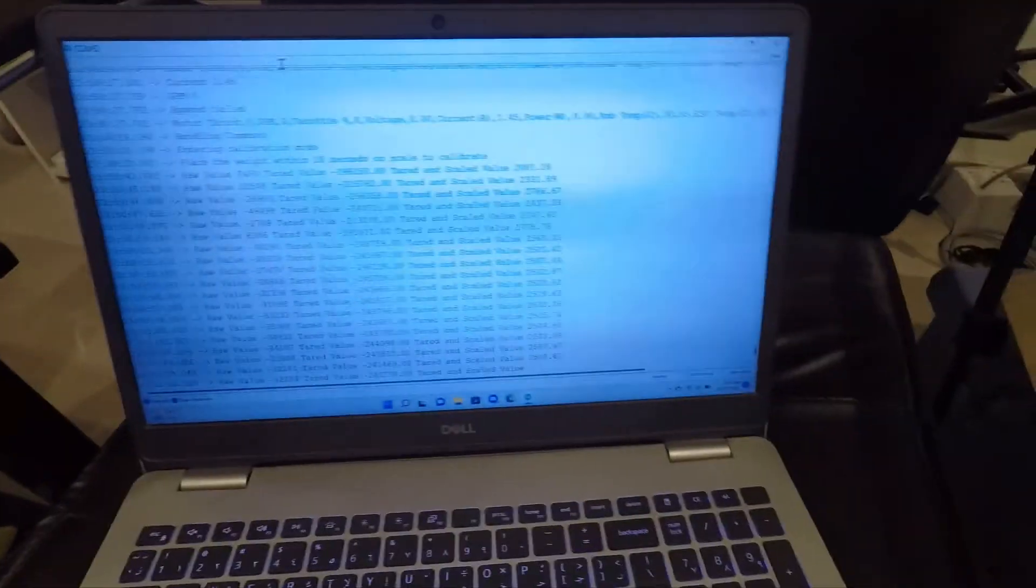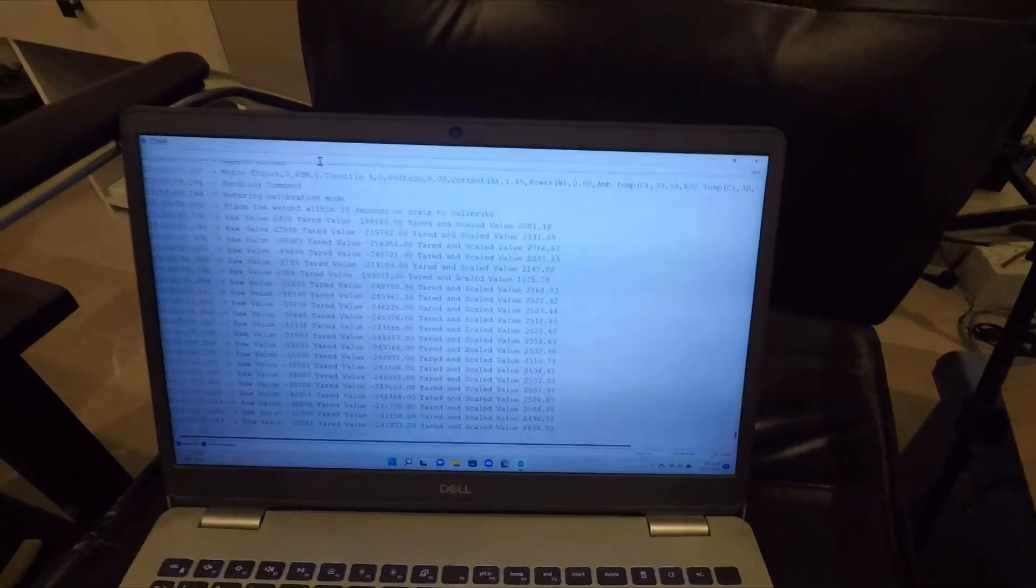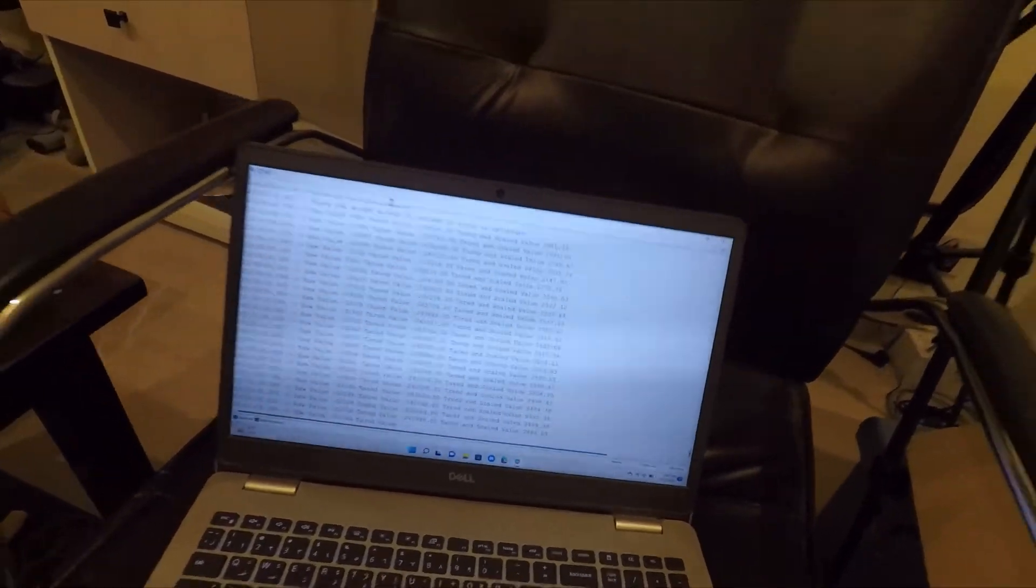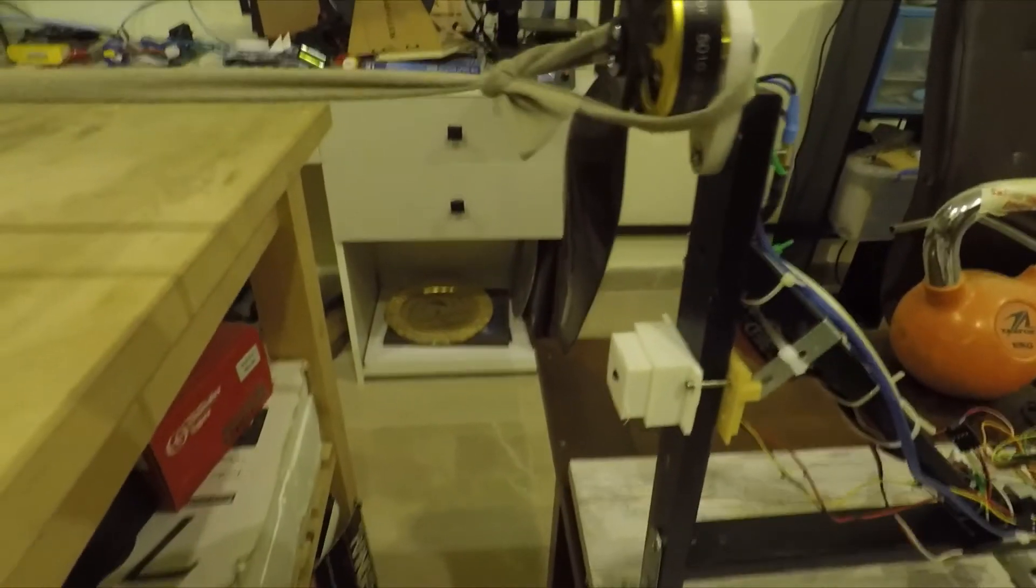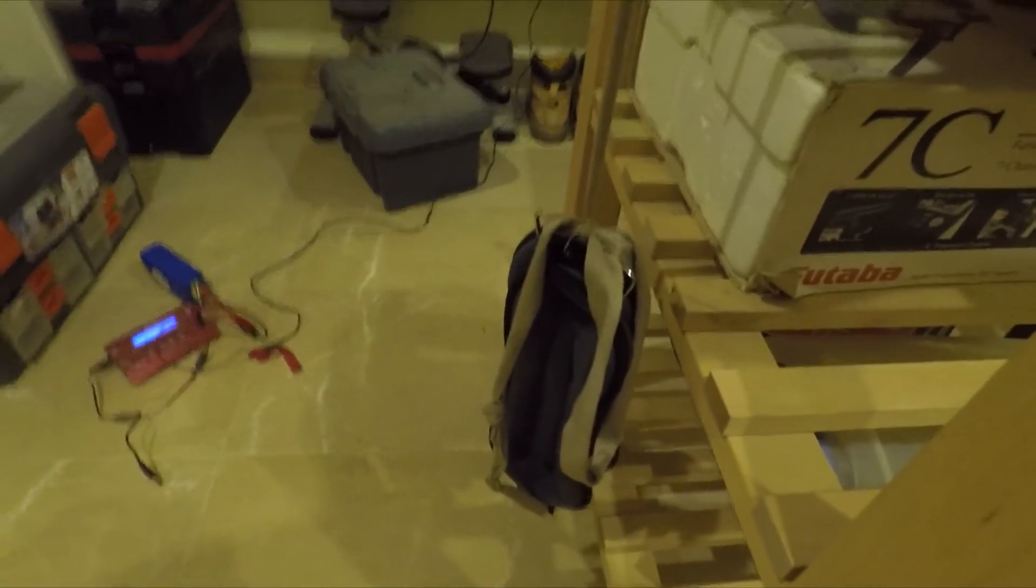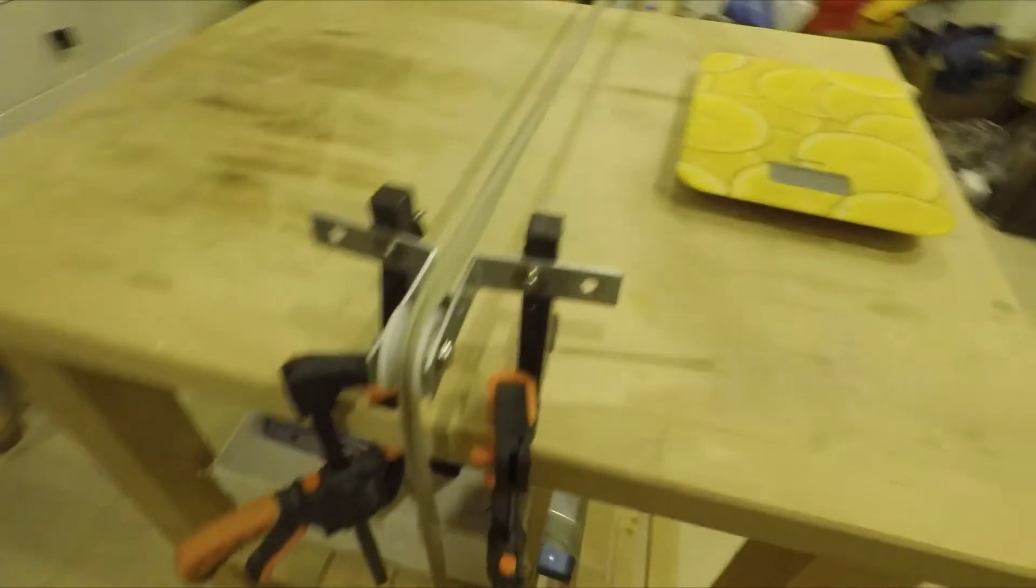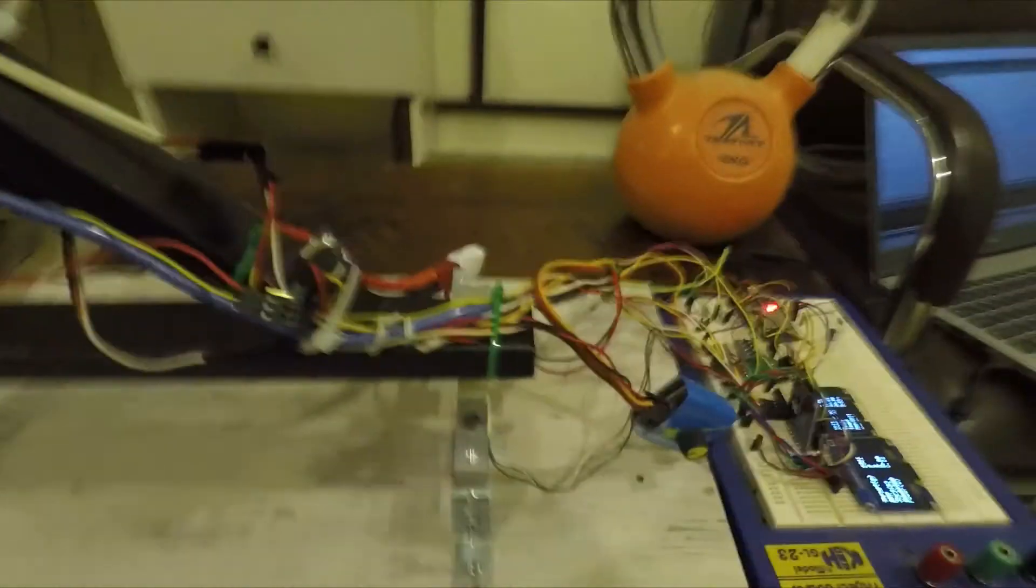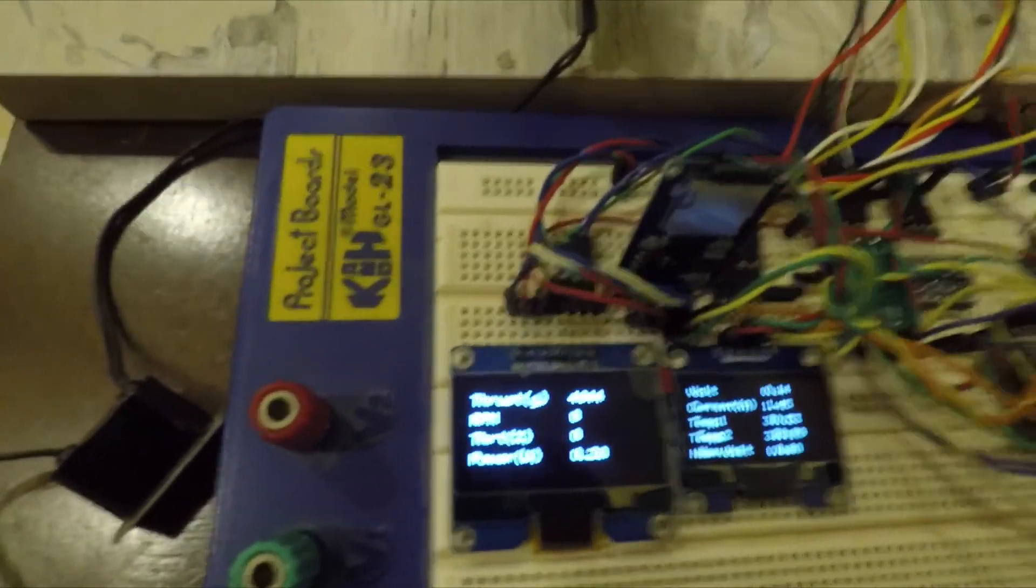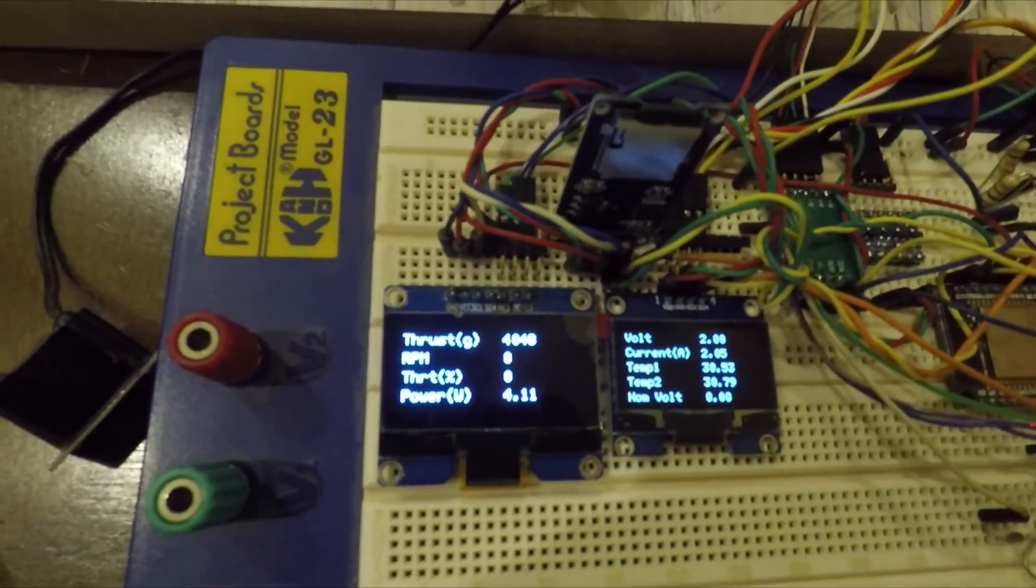To verify that the calibration has been done correctly, now we can apply a different weight and see if the system measures it correctly. For this, I will use four ankle weights, so a total of about 4000 grams. So here I have connected the 4000 grams of weight. The system is in tension so all the load is fully applied. And we check on the screen, and we see that the weight that's applied on the screen is 4000 grams, which indicates that our calibration was successful.